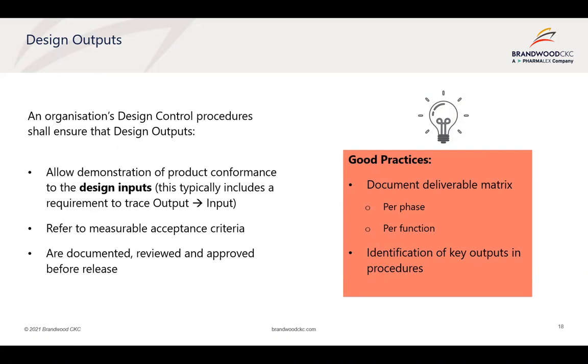It's always good to refer to measurable acceptance criteria, an aspect we'll cover in the verification and validation sections as well. All of the outputs generated as part of design and development have to be documented, reviewed, and approved before release as part of your documentation control procedure.